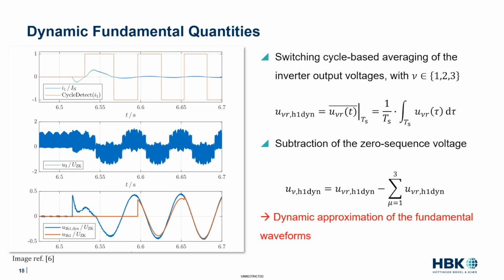And if you compare that average, which gives you an impression of the fundamental inverter output waveform, with a conventional method, then we have again the same effects. The conventional fundamental voltage calculation based on a Fourier series also depends on the fundamental period. And therefore, you get the first value here only after the first full cycle has been detected. But there are a few more issues. One is that during the startup process, the frequency and the amplitude of the inverter output voltage increase continuously. Therefore, the quantities are not periodic.